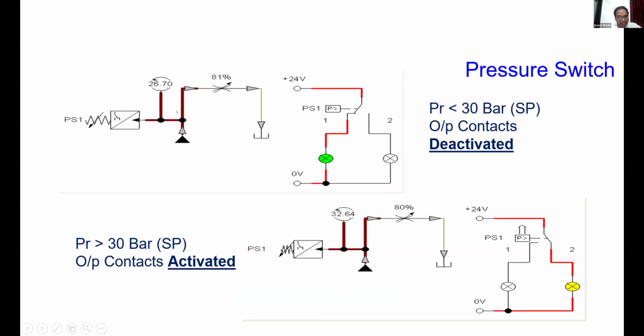Here I am getting pressure continuously, and I have connected the sensor here, guys. I am getting plus 24 volt here as the sensor is a DC sensor. And if I get the value of 30 bar, which is the set point, at that time this contact will change. You can see in this diagram, once this 30 bar is achieved, this contact changed. Now this valve is open. So the sensor works as per how exactly you are providing the set point to that particular sensor.